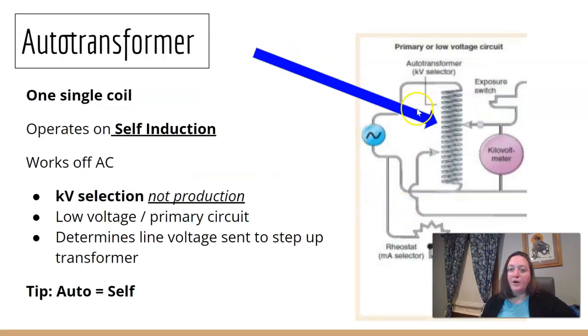Your auto transformer is the first transformer we hit. It has one coil. It operates on self-induction because it's lonely. It doesn't have any friends. It's a coil by itself. Again, it works off of alternating current. We are selecting our KV here, not producing it. Watch that word. So we're selecting our KV, and the kilovolt meter here is going to determine the voltage being sent up to the step up transformer. So I want you to think auto is self. It's also selecting my KV.